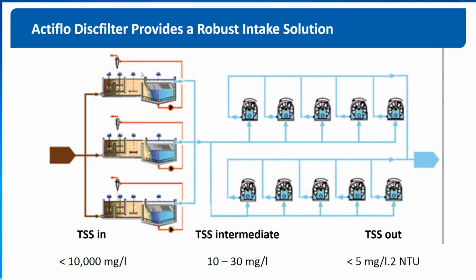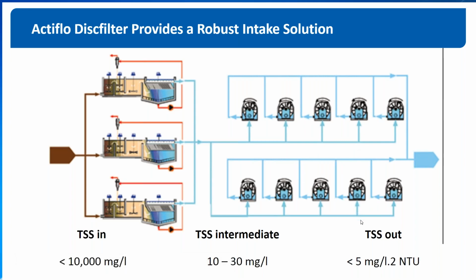So in this process, coagulant and flocculant will be dosed at the Actiflo and mixed together with a micro sand. The micro sand will enable the settling of most of the solids, and then it is returned through a hydrocyclone where the sand and the solids are separated and the sand is reused. The solids are then discharged. The filtrate out of the Actiflo passes on to the Hydrotech filter for polishing. And what you can expect out of the Hydrotech filter, in the best case, is 5 milligrams per litre or 2 NTU.